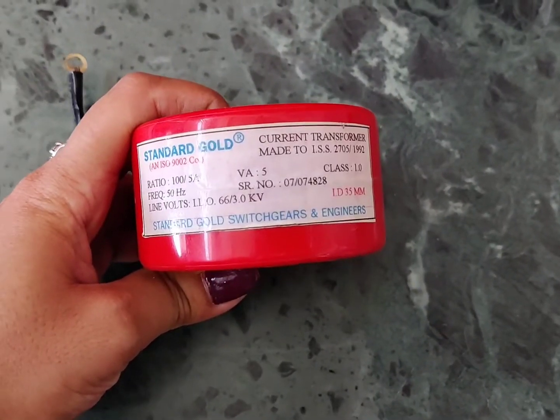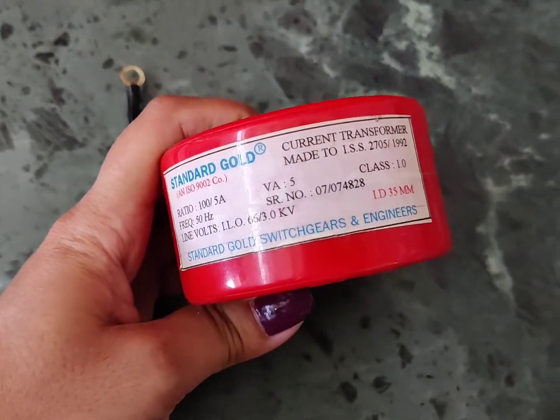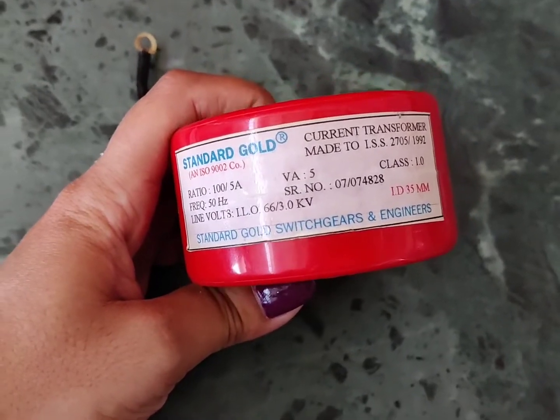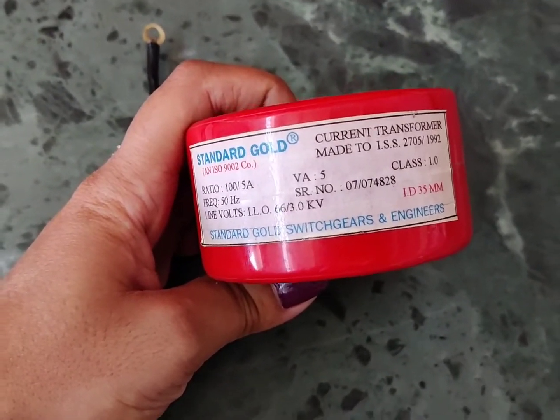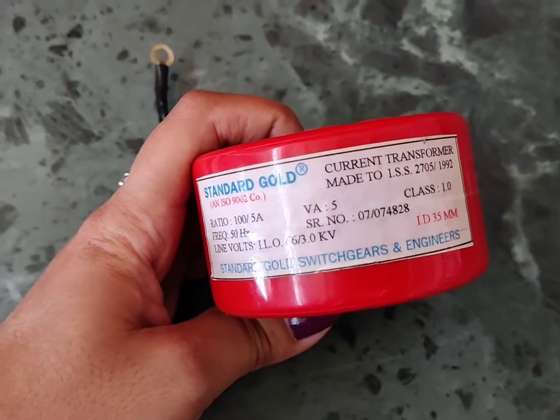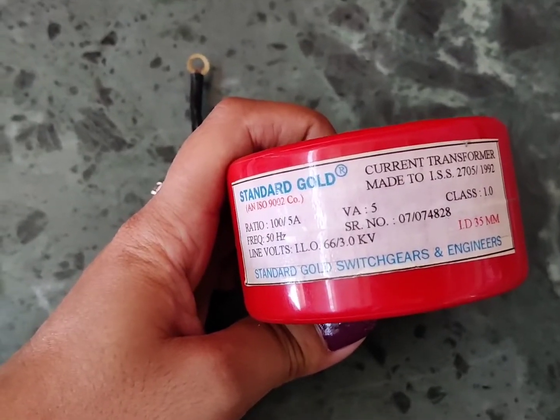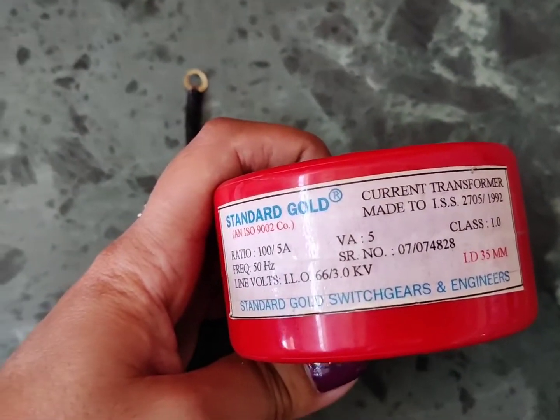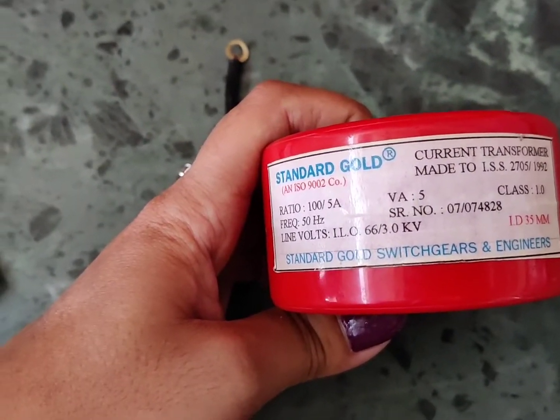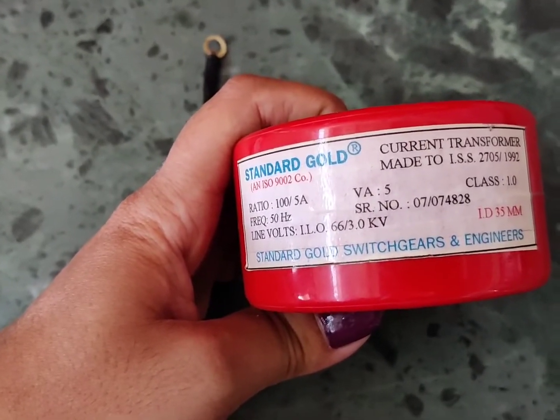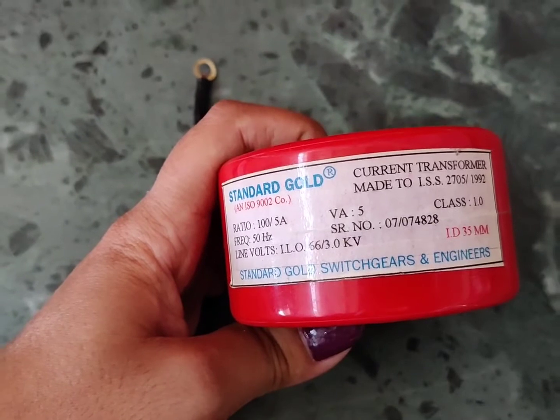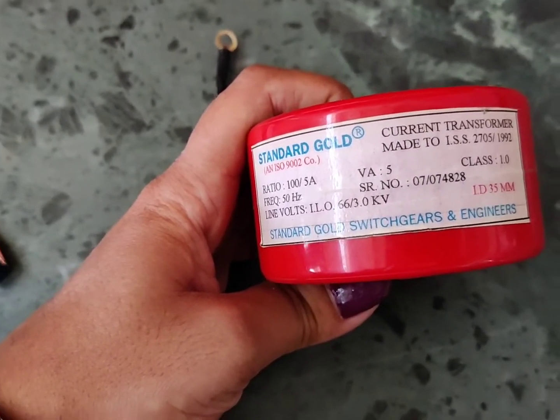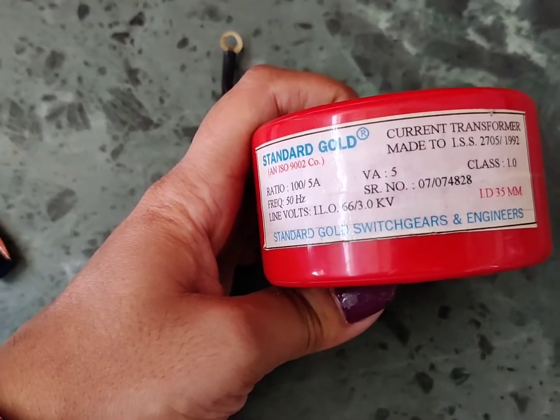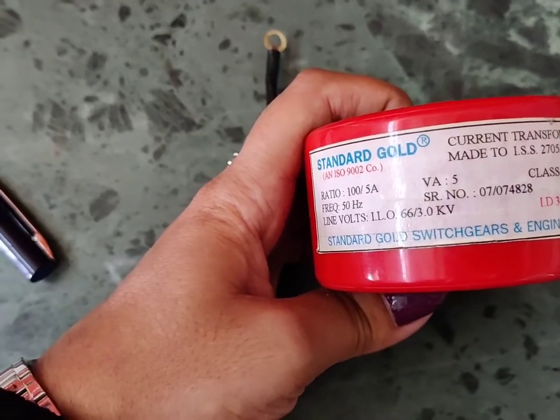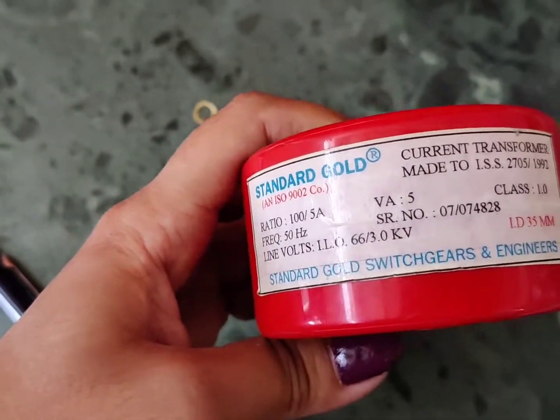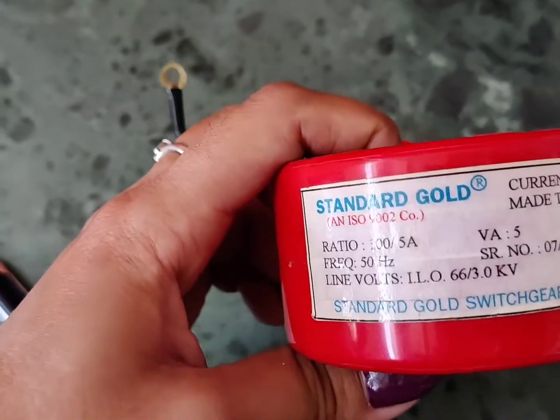So the next protective device are the current transformers. So these are nothing but the instrument transformers. We have already discussed the instrument transformers in the electrical measurement. So basically the function of the current transformer or CT is to step down the current. So in case of power system, CTs are used to step down the fault current and then give that reduced current to the protective devices, because whenever a short circuit or any type of fault occurs in the power system, the current rating of that fault is very high, and that large amount of current cannot be given to the protective devices, or else the size of the protective devices will become very large. So what we do is we step down that current, we reduce that current with the help of the current transformer, and then we give that current to the protective devices for purpose of protection.